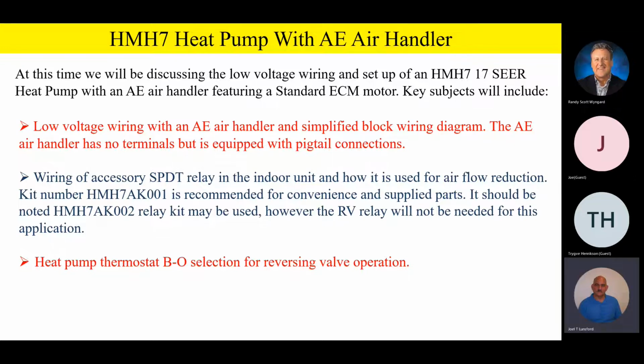It should be noted that the HMH7AK002 relay kit may be used. This is kind of the universal kit because it can be used on any of the products, AE air handlers, variable speed air handlers, furnaces, etc. However, the RV relay on the 002 kit will not be needed for this particular application. For the AE air handler, simple application, the 001 kit is just the simple relay kit. The 002 kit has all the same stuff in it, except it has 2 relays instead of 1. That's an easy way to remember it: the 001 kit has 1 relay, the 002 kit has 2 relays.